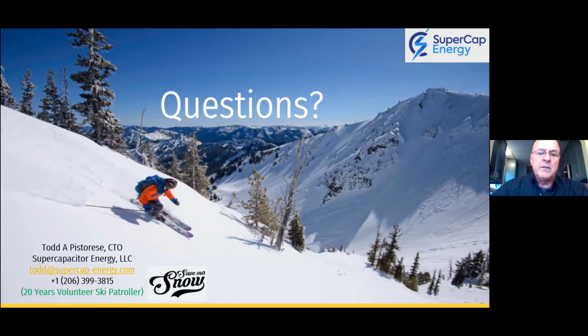Are you able to throttle energy discharge of supercaps well enough for them to provide storage over a couple of days? Yes. The energy discharge is pretty much controlled by the inverter, and loads pull energy, capacitors don't push energy. But there's a capacitor management system in the supercapacitors themselves that controls the rate of discharge up to about 100%. You can go as high as what they call a 2C rate in most of them—that's typically how they design them, which would be 100% discharge in half an hour. But most of the throttling and control is done by the inverter and whatever the demand is from the loads.